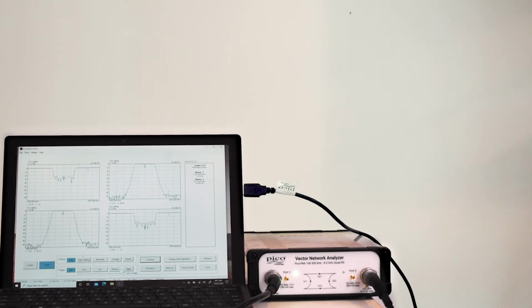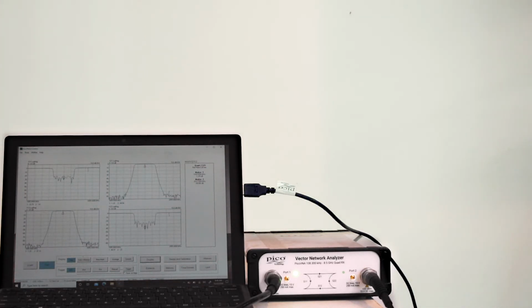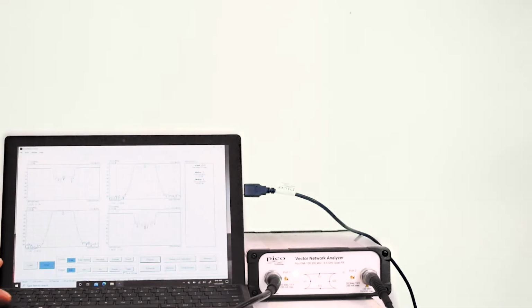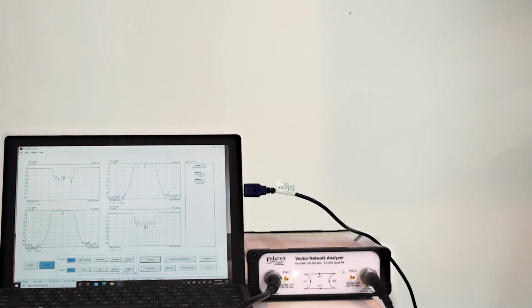Then, in the PC, open the PICO VNA software. In the main menu on the PC screen, select Tools and Calibration Kit. Click Load Port 1 Kit, insert the data for the Port 1 kit, and click Apply. Similarly, click Load Port 2 Kit, select the data for the Port 2 kit, and click Apply. The next step is to choose calibration kits appropriate for the device under test. If testing a non-insertable device under test with, for example, female connectors, use a single female kit for both ports in the VNA module.